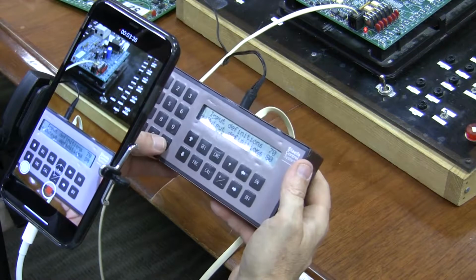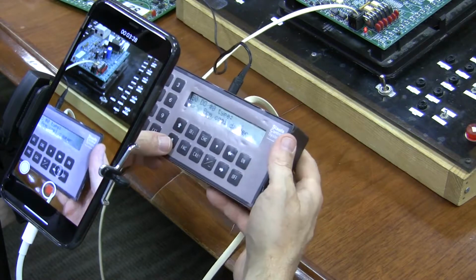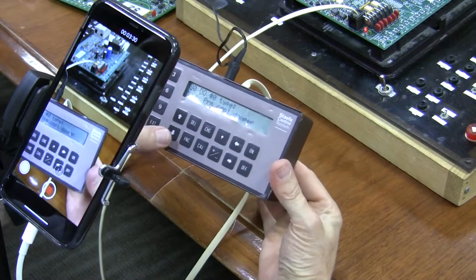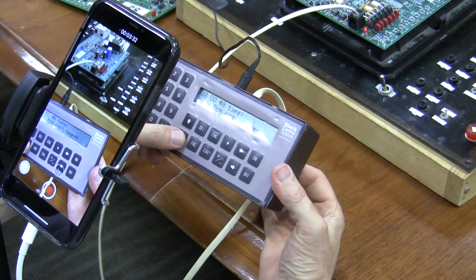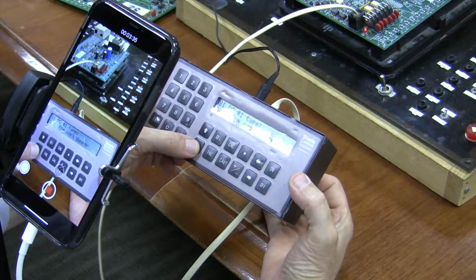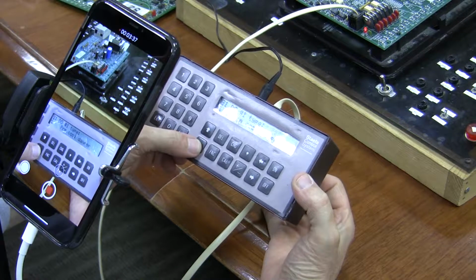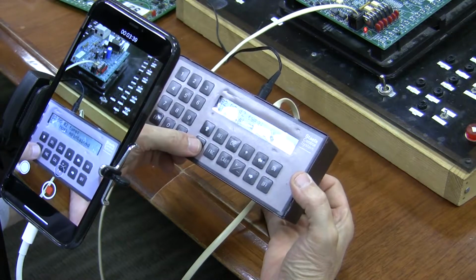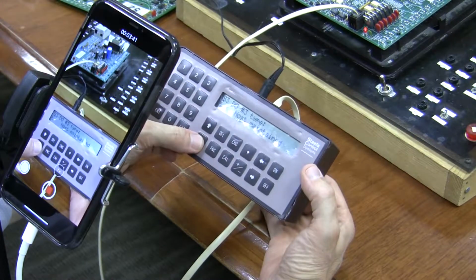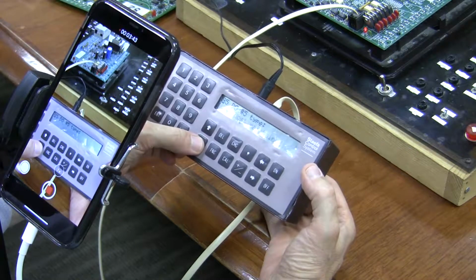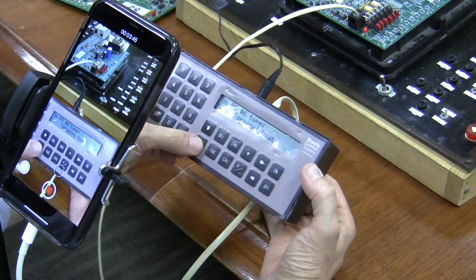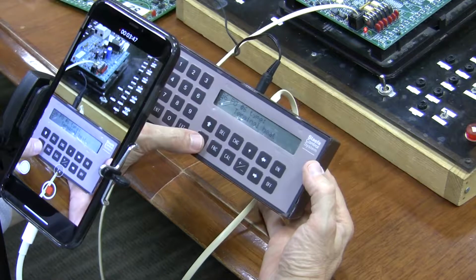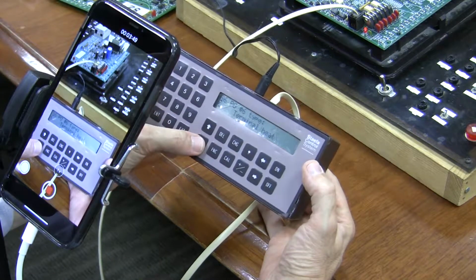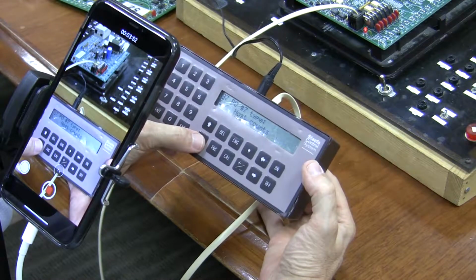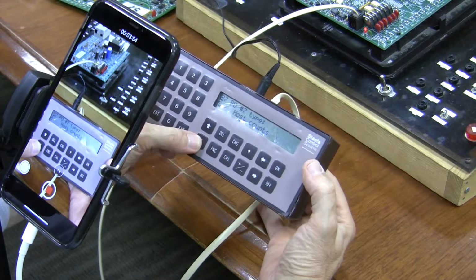So if I hit enter on this, I can see that it thinks it has a primary cool damper wired up to digital output 0. It thinks it has a primary cool damper wired up to digital output 1. It doesn't think it has anything wired up to output 2, output 3, output 4, output 5. It thinks it has a terminal heat valve wired up to output 6. And it doesn't think it has anything wired up to output 7, and that's all the outputs there are.